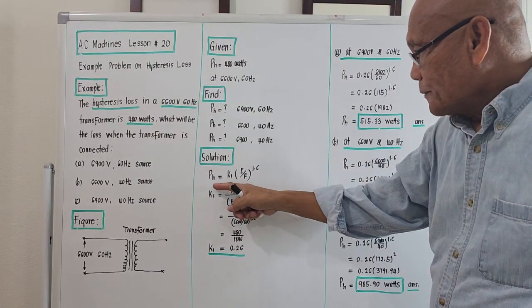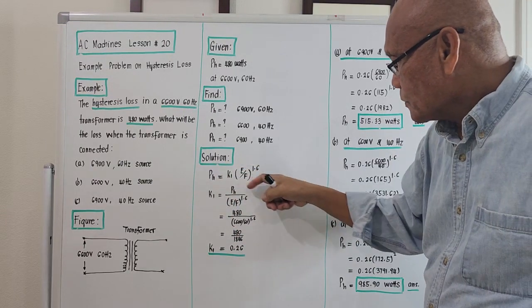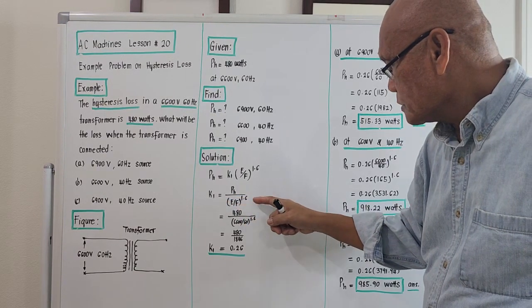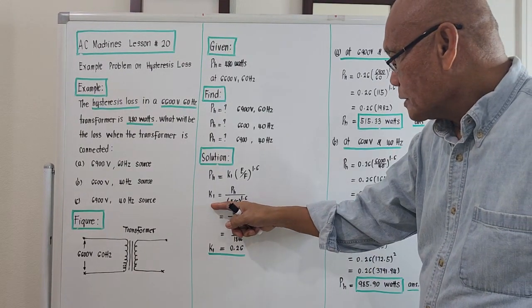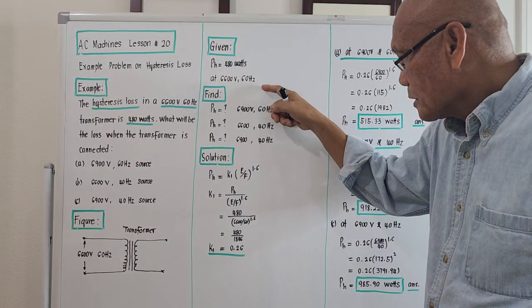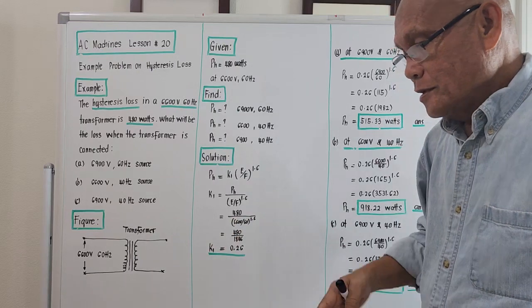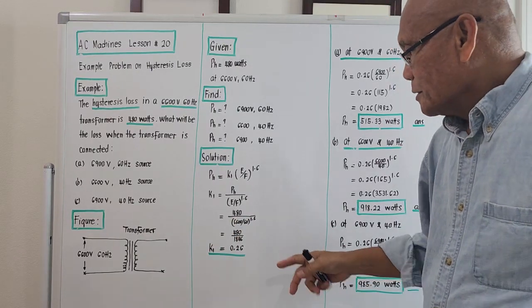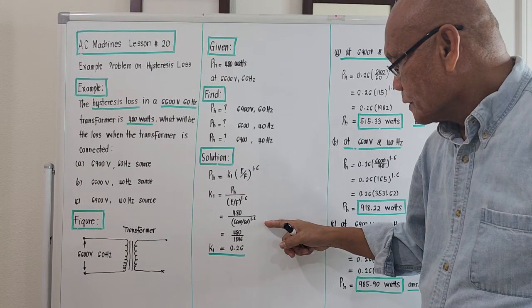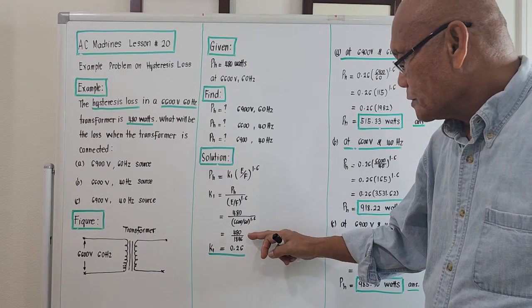From this equation, we'll compute for k1. k1 will be Ph divided by the quantity E over frequency, raised to 1.6 — meaning the ratio of voltage and frequency raised to 1.6. To solve for the constant of this transformer, k1, we'll use the initial condition: at 6600 volts and 60 Hz, the hysteresis loss is 480 watts. So k1 equals 480 divided by 6600 over 60 raised to 1.6. I calculated 6600 over 60 raised to 1.6 on the calculator — that gives approximately 1846.